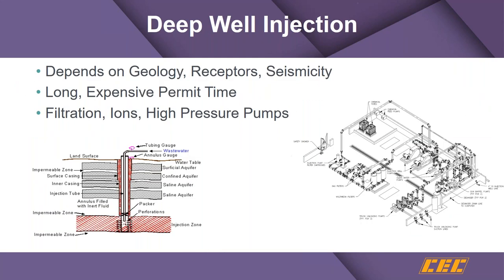In areas where the geology is acceptable, deep well injection has been practiced. A number of landfills in Michigan have that right now. It requires significant pressure on the order of 1,500 PSI. Some filtration is needed to avoid blocking the geologic environment, and some chemical reduction must take place — for example, barium sulfate is going to precipitate at around 5 milligrams per liter, so you must be aware of chemistry to avoid solids blocking the geologic formation.